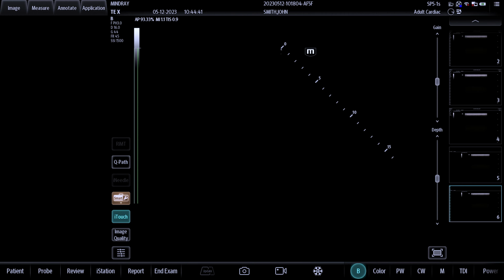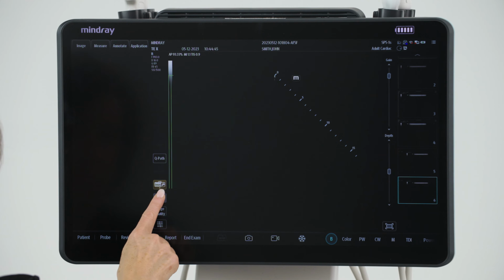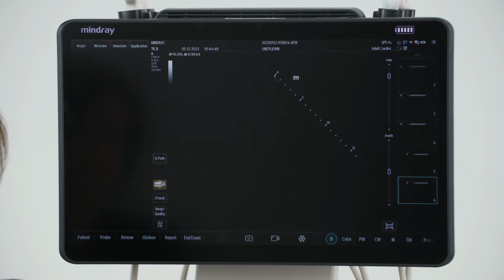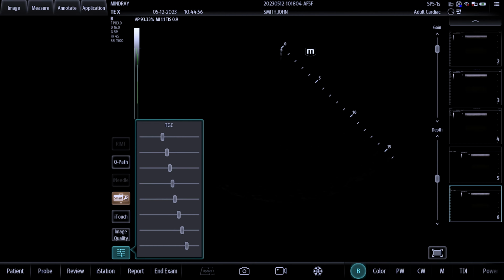Once it is pressed, the key will stay highlighted blue. To turn it off, press and hold the iTouch key. iTouch can be used in both B mode and PW mode. The TGC icon tab controls the time gain compensation, which allows for fine-tuning of gain in depth-dependent zones.